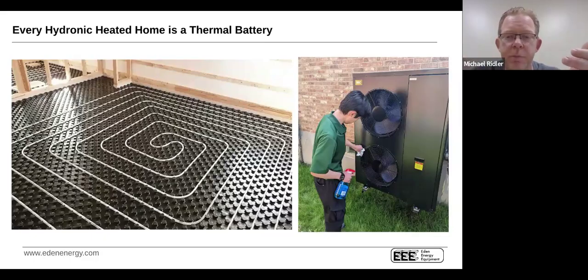If you install an air-to-water heat pump and load shift when you're heating the mass of the building, not only do you take advantage of a very high COP—efficiency up to 300%—but from an electrical grid standpoint you can tell your local operators: if you want to advocate for heat pumps, just don't specify what kind. Air-to-air, great. Air-to-water, also great. We can take a boiler out, replace it with an air-to-water unit that does heating, cooling, and domestic hot water.